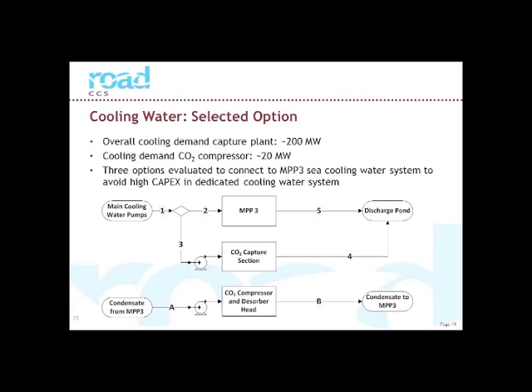Part of the cooling is done by using condensate from the steam system of MPP3, shown at the bottom side of this slide. As said, we use it to cool the CO2 flow from the stripper before it enters the compressor. The cooling load is about 20 megawatt of the stream, and the advantage of cooling with this condensate is first that we have a smaller seawater cooling system, and secondly the heat recovery gives an improved efficiency at the power plant.